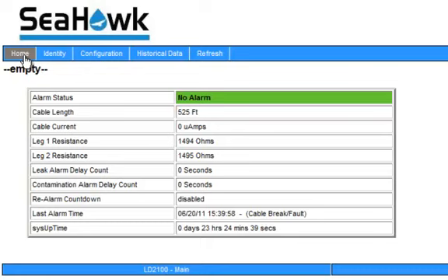It's at this point recommended to generate a leak on the system to make sure that our virtual zones show up correctly. Right now we're generating a water leak on the end of the system. The controller is going through its countdown. So once the time frame passes, we should get in our alarm status our leak detected at our footage, and then also see our label being assigned to that footage. At this point, you can clear the leak on the system.